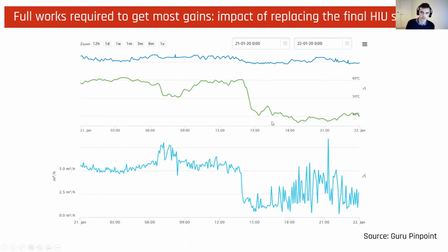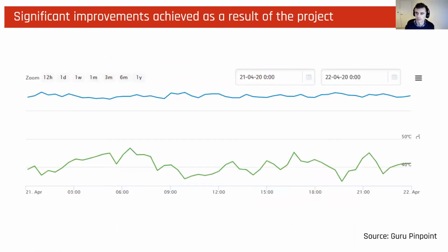So we have the flow temperature at 70 degrees, and really the discussion here is how do we get it down? Actually, we could reduce the flow temperature here down to 65 degrees initially. That shows that we've had a big impact on the system heat losses, and also helps to prepare the system for future decarbonisation. At the moment it's currently operating at 65, 40 or 45, and the next step is to look at how we can bring that down further. The key point is that on this site we don't need any more invasive works. It's simply a case of tweaking the performance of some HIUs and going forward with some commissioning adjustments on them.